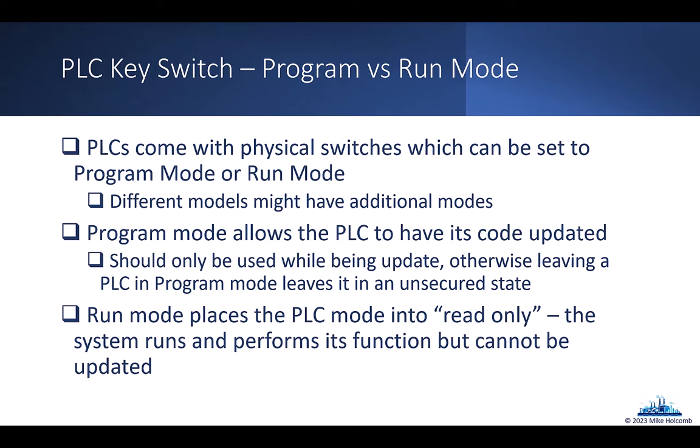Now, if you have somebody make changes to a PLC, maybe they're doing an update in a maintenance window and updating firmware, or maybe they made an adjustment to the programming code on the PLC, and they forget to put the key switch back into run mode, that's where we get into trouble. Because if an attacker is in the environment, they find the PLC, and then they find that it's in program mode, then they could potentially make changes either to the firmware or to the code running on the system. But it's really that easy that we can protect PLCs if the key switch is over in read-only mode.